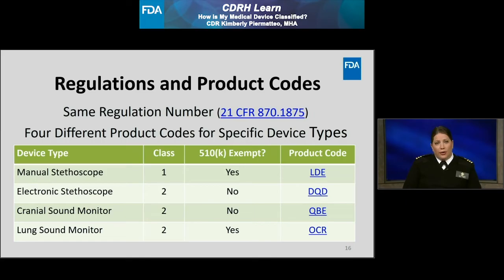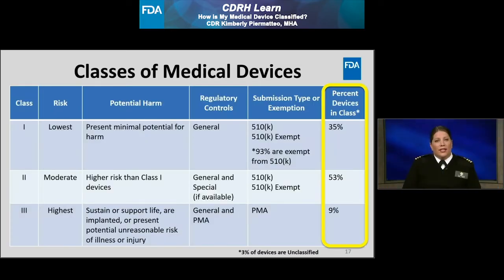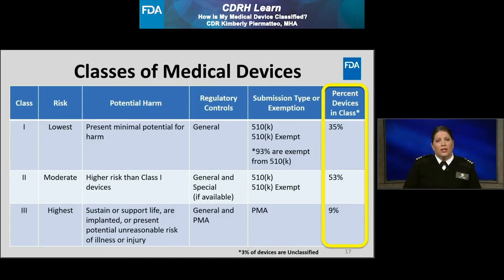Determining the appropriate product code will help you determine the extent of regulatory requirements for your device. The last column of the Classes of Medical Devices table provides insight into the percentage of devices in each class. Out of all regulated medical devices, roughly 35% are Class 1, 53% are Class 2, and 9% are Class 3. Roughly 3% of devices are unclassified — a device which was in commercial distribution prior to the Medical Device Amendments of 1976 and has not yet been classified into Class 1, 2, or 3.